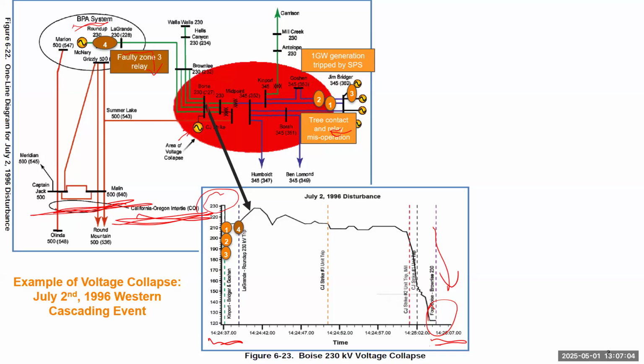Some transmission lines also have a zone 3 relay, which covers your neighbor's neighbor. If your neighbor's neighbor has a short circuit, but your neighbor doesn't trip, then you need to wait for some time and trip. But when the system is operated at a highly loaded condition, it can be very tricky to differentiate a real short circuit from an overloaded condition. So this zone 3 relay misoperated and tripped the line. It believed there was a short circuit in that area. So that became almost the only transmission path sending power to this area, but that one is also open.